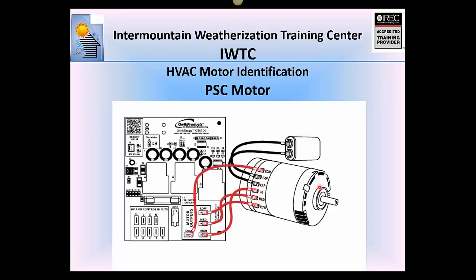A PSC motor — Permanent Split Capacitor — will always have a remote capacitor attached to it. There will always be two leads running to that capacitor, typically brown and brown-and-white, though you may find other colors like purple or blue. That's the origin of the name Permanent Split Capacitor motor. It's the most common motor found in furnaces, especially older ones.